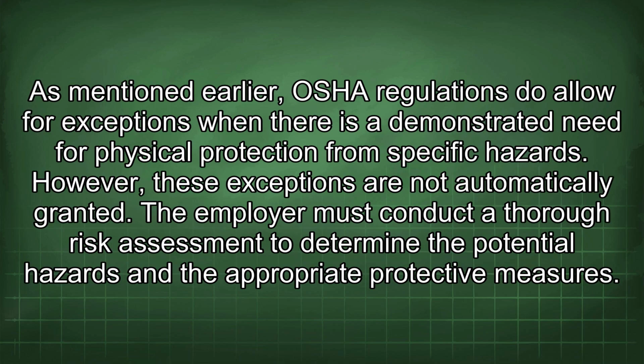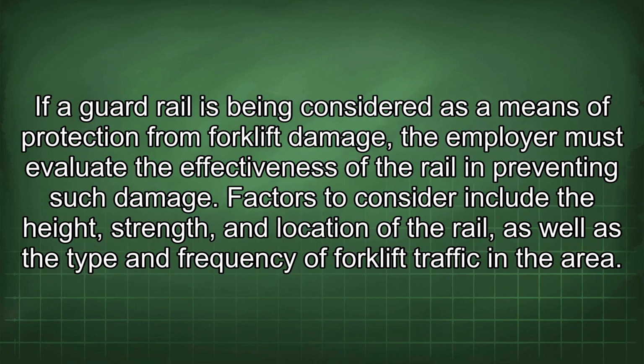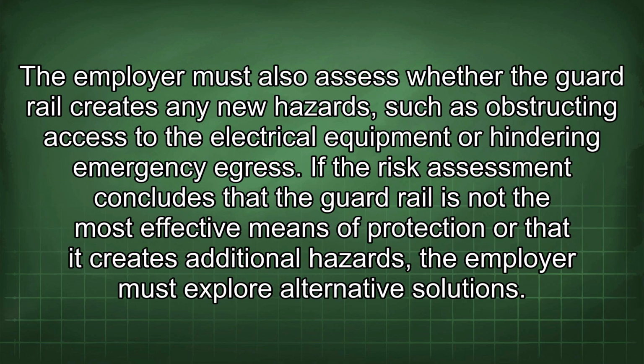As mentioned earlier, OSHA regulations do allow for exceptions when there is a demonstrated need for physical protection from specific hazards. However, these exceptions are not automatically granted. The employer must conduct a thorough risk assessment to determine the potential hazards and the appropriate protective measures. If a guardrail is being considered as a means of protection from forklift damage, the employer must evaluate the effectiveness of the rail in preventing such damage. Factors to consider include the height, strength, and location of the rail, as well as the type and frequency of forklift traffic in the area. The employer must also assess whether the guardrail creates any new hazards, such as obstructing access to the electrical equipment or hindering emergency egress.